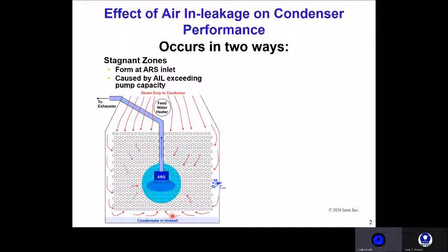Carbon dioxide is a small percentage of the partial pressure present in these zones, but additional chemical reactions can allow for carbonates and bicarbonates to be produced in the condensate. So the zone of high partial pressure essentially reduces the overall surface area of the tubes, contributing to excess condenser pressure, and may introduce dissolved oxygen and other compounds in the condensate.